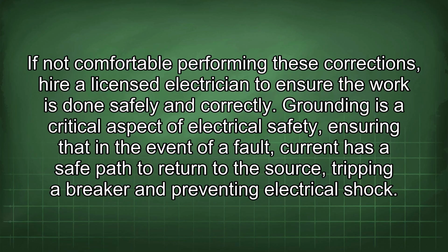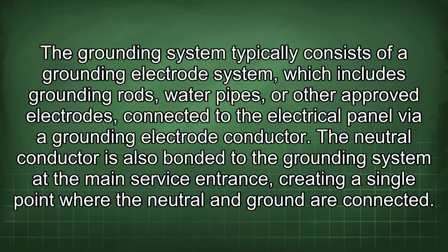Grounding is a critical aspect of electrical safety, ensuring that, in the event of a fault, current has a safe path to return to the source, tripping a breaker and preventing electrical shock. The grounding system typically consists of a grounding electrode system, which includes grounding rods, water pipes, or other approved electrodes connected to the electrical panel via a grounding electrode conductor.